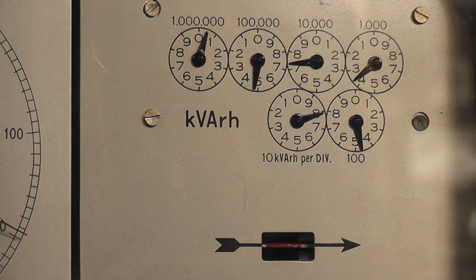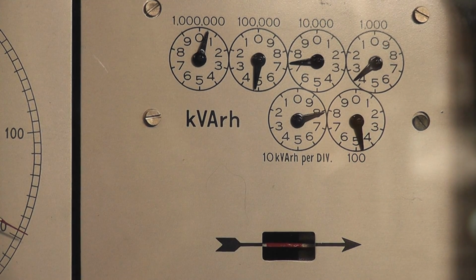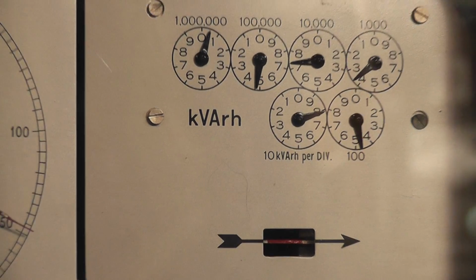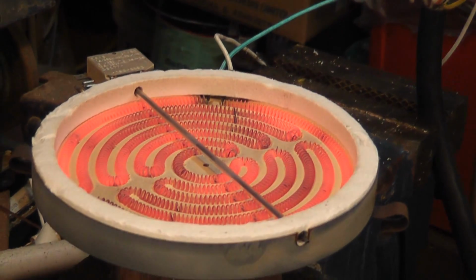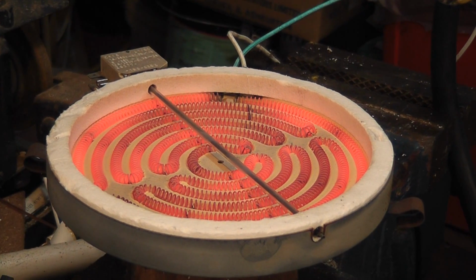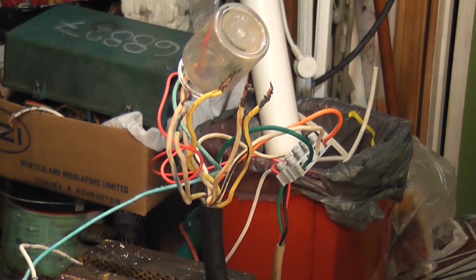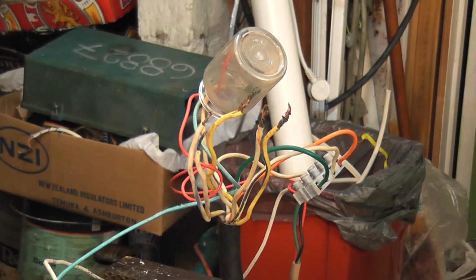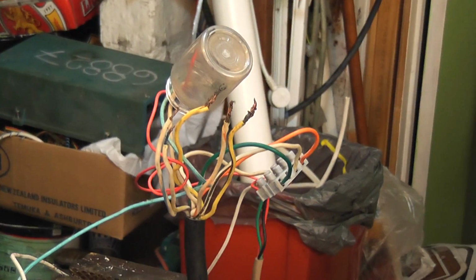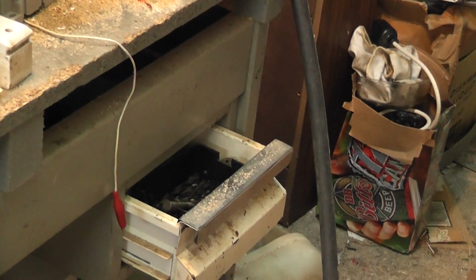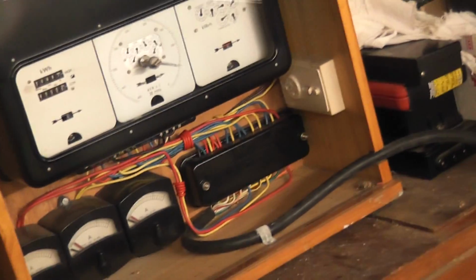I'll show you what the load is. Just got a 2 kilowatt element sitting here temporarily connected to this multi-core cable, which is 10 core cable to control the meter. The cable goes through the ground here. Oh, that's my foot. Ground and into the box.